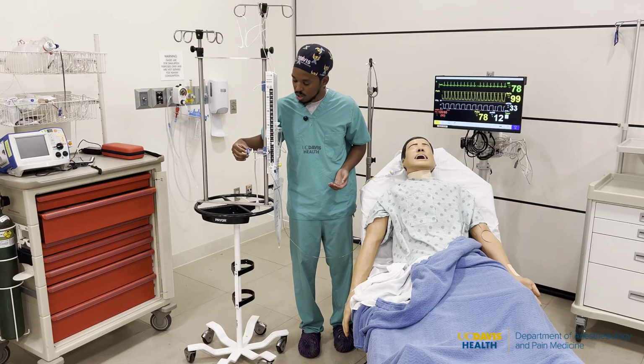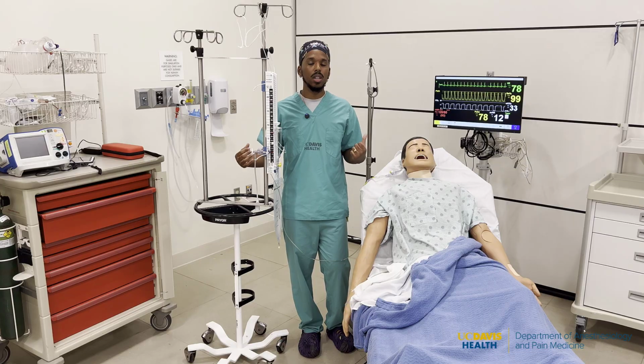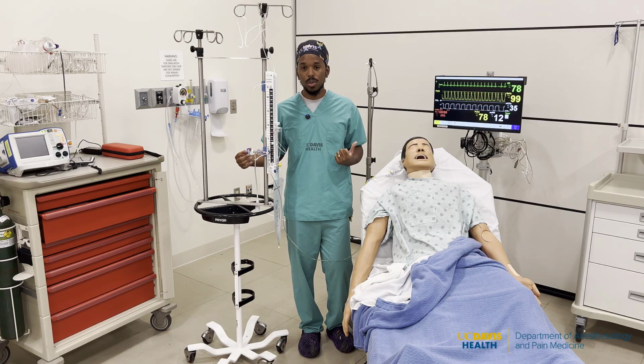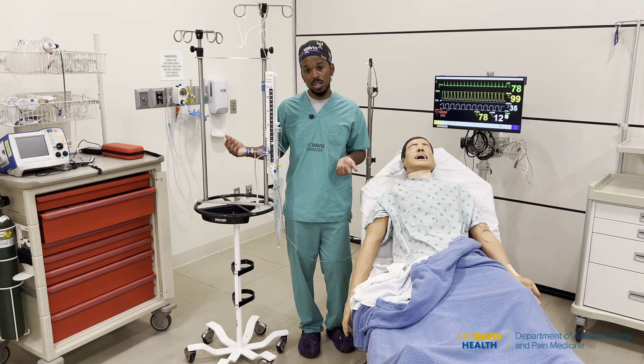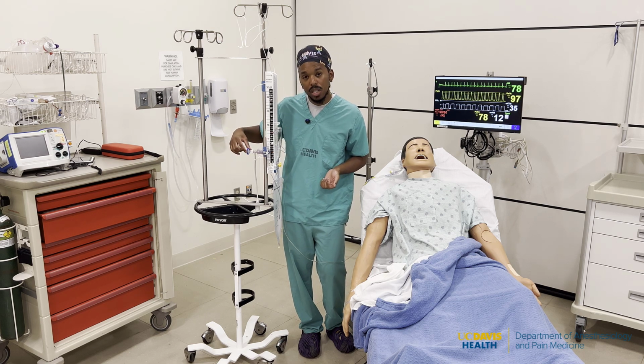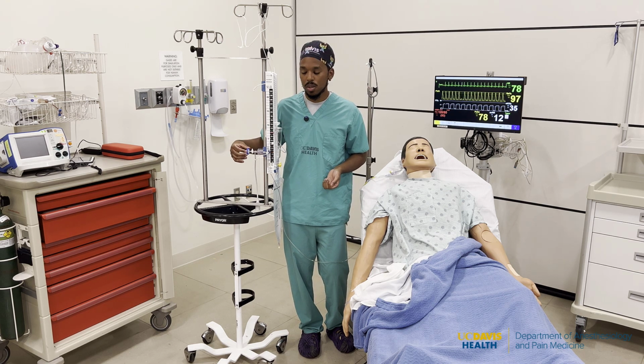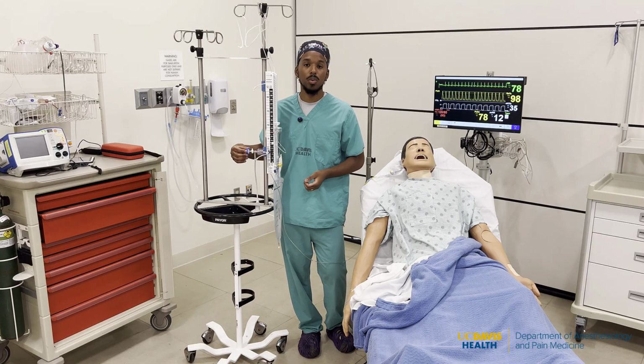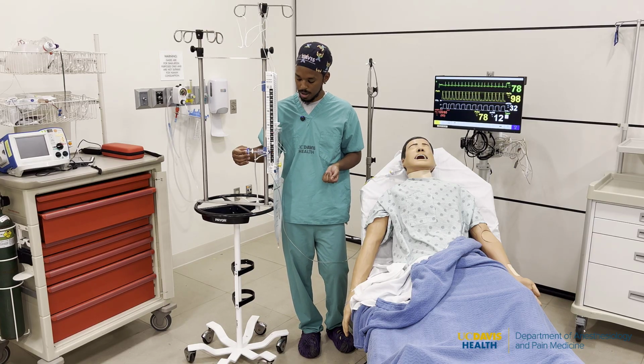And then, important thing to note about this filter: if you're ever having malfunctions or poor waveforms, one thing to troubleshoot is to consider that this filter may be compromised or wet. And if so, all you would have to do is remove this filter and replace it. So just something to keep in mind.